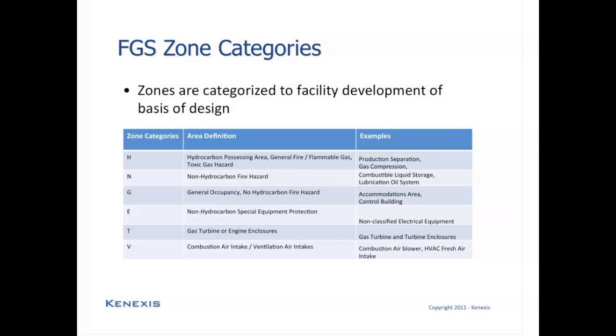The next type of category is a T, which is dedicated to gas turbine enclosures or engine enclosures. These types of areas have very specific and in some cases very prescriptive requirements for the type of fire and gas equipment that are going to be required. Finally, there is a type V, which is dedicated to air intakes or ventilation. So ventilation air intakes into occupied facilities, and also combustion air intakes. And again, like E-type zones, V-type zones are primarily concerned with segregating the hazards of the process area, of flammable or toxic gases, and preventing those hazards from migrating into another area through an intake system.